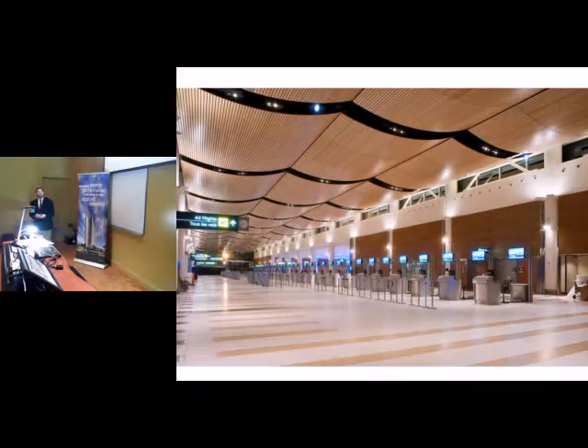This causes all sorts of motion in the space as air gets entrained into that jet. The overall effect is excellent air movement in the departures hall with very little input from the fan. It's also been commented that the air quality in there is exceptionally high because of that good mixing of fresh air being pushed into the space. There are no pockets of dead air that anyone's observed.